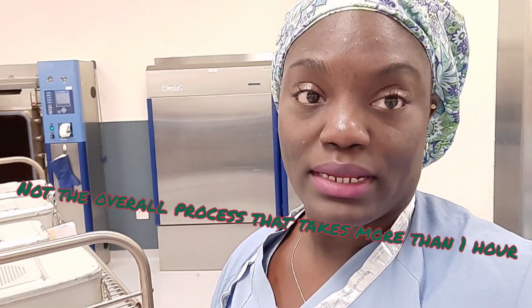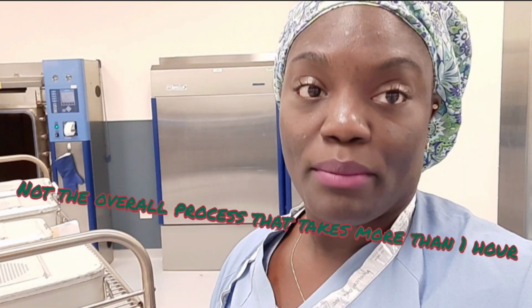Now, majority of the sterilization is done in 4 minutes. Hey guys, just wanted to clarify for a quick second. I didn't mean the overall process was 4 minutes. The sterilization process from start to finish is about an hour, but the dedicated time on a sterilizer to sterilize something is 4 minutes. And that is according to the IFU, and you have to follow the IFU. That is the manufacturer instruction for use.